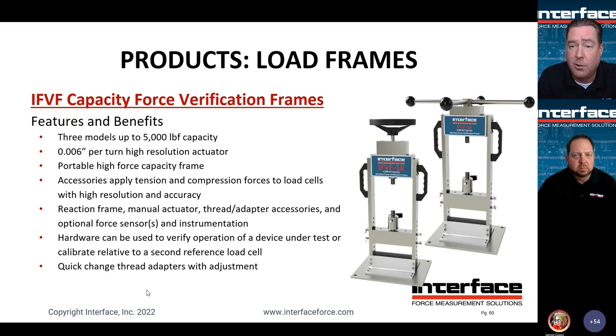This can be, and we have successfully, combined with our portable load cell calibration system, and it's given us great results. This consists of the actual frame. We have essentially a threaded rod that provides the force application through the lever on the top, or the wheel on the top in the lower capacity cases. And then you'd pair that with a reference standard load cell, perhaps a different calibration adapter set to fixture into the cell itself, or the frame itself, and then some sort of a display to indicate the values from the standard and the device under test.